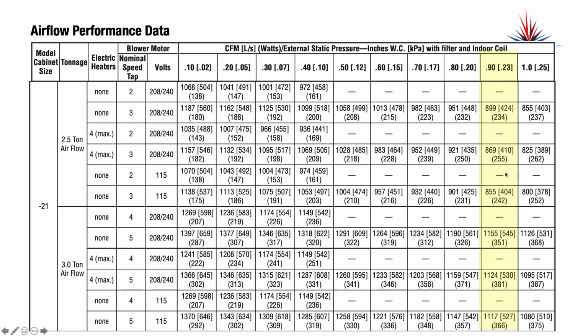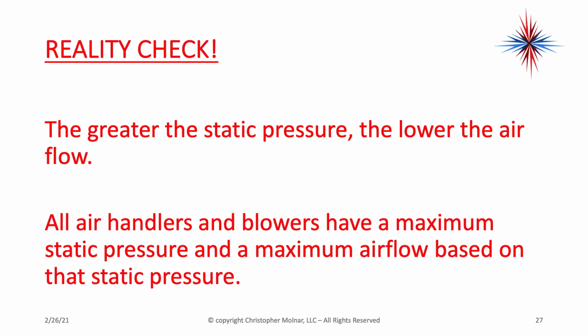Remember, I need 1,000 or 1,200, okay? I'm too low. So all of a sudden you see where static pressure is affecting my airflow and my performance. Once I hit the max static pressure, it is so far out of range. If I go over that, I'm going to have major issues. That's why every unit has a maximum static pressure. It's for this exact reason.